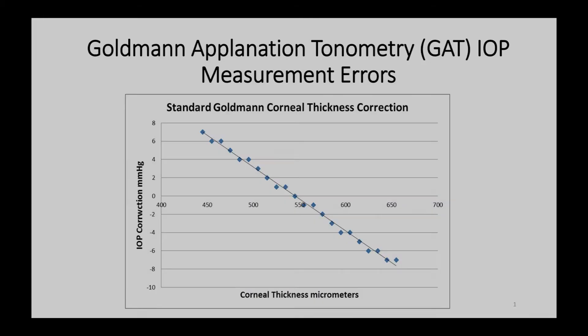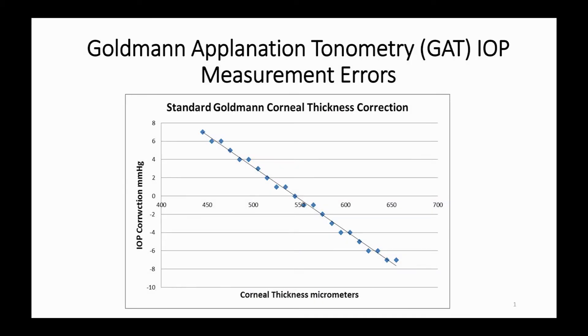It has been demonstrated even by Goldman himself 60 years ago that several IOP measurement errors are present. Those errors include corneal biomechanical errors of central corneal thickness, corneal rigidity, and corneal curvature.